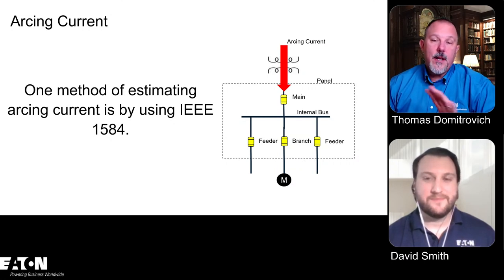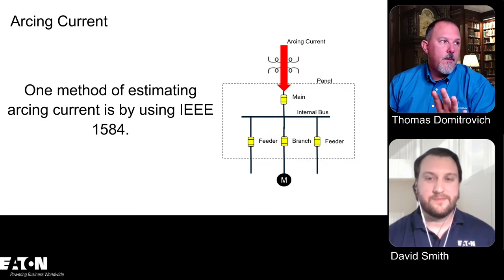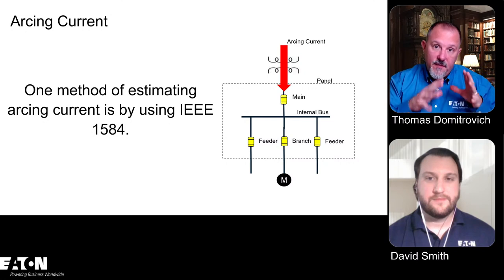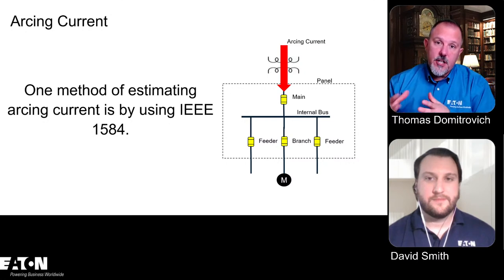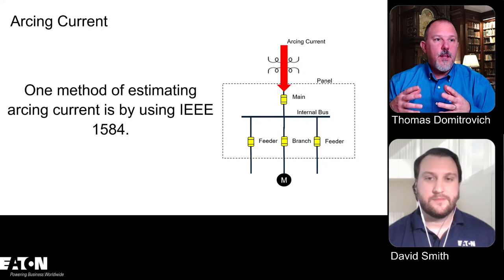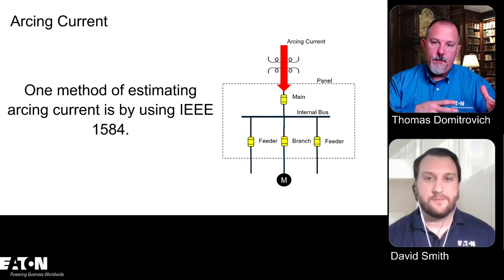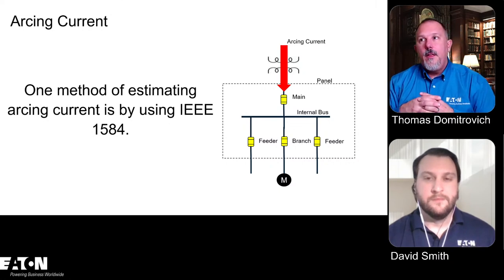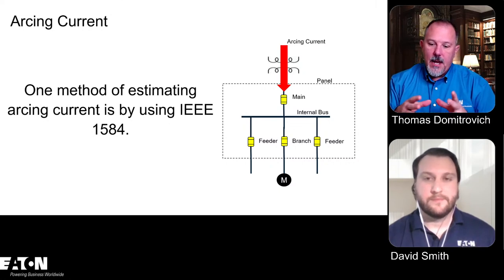So here's what I learned. What we learned was that he had an actual event. He used the arc reduction maintenance switch. With the maintenance switch on, the electrical workers were working in a piece of equipment. They accidentally touched an energized piece of equipment with the chain of a come-along. There was a little blue arc. Now, we calculated, based on IEEE 1584 and the arc reduction maintenance switch, like 2-point-some calories.